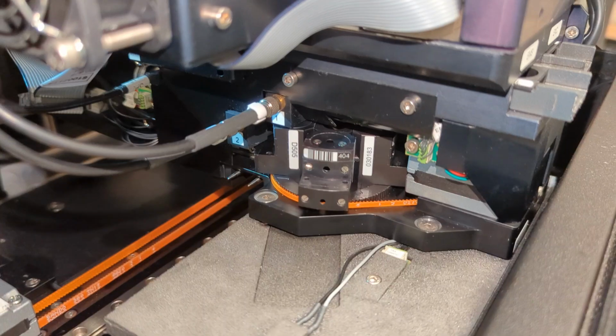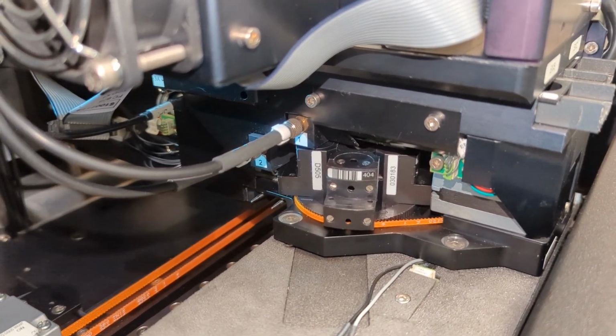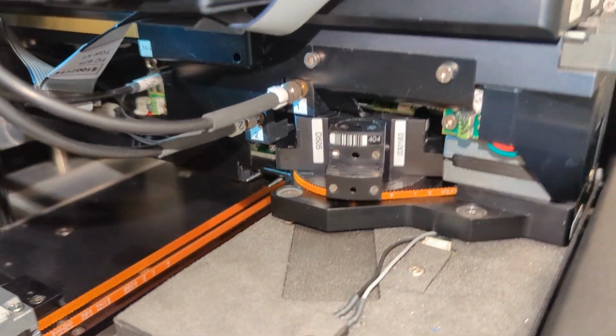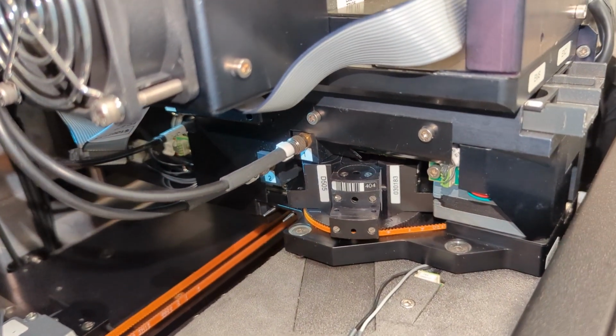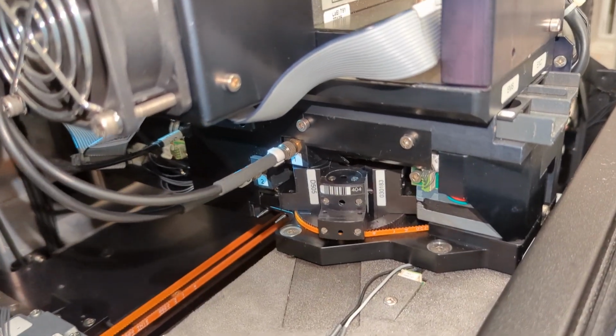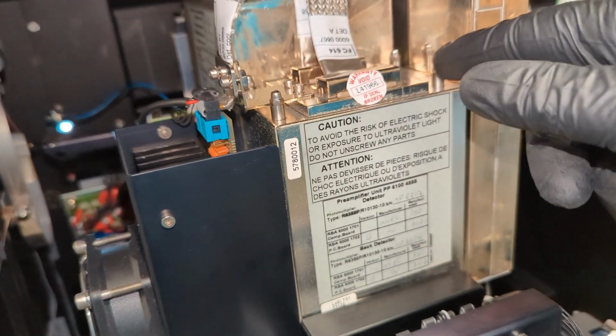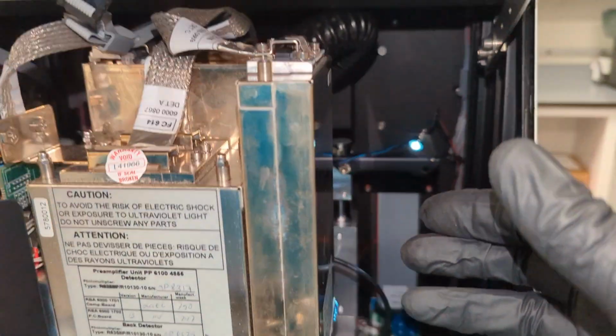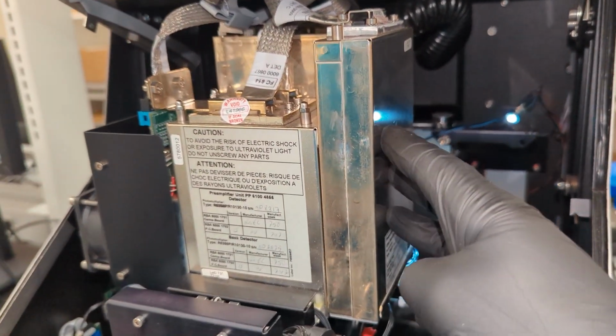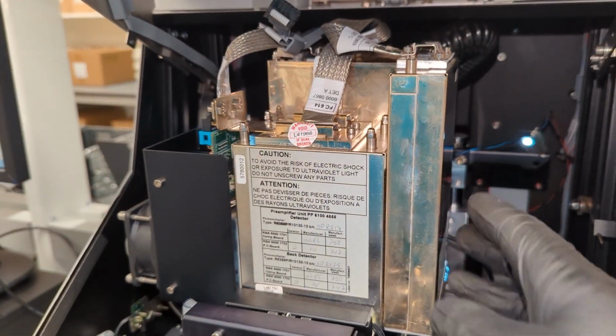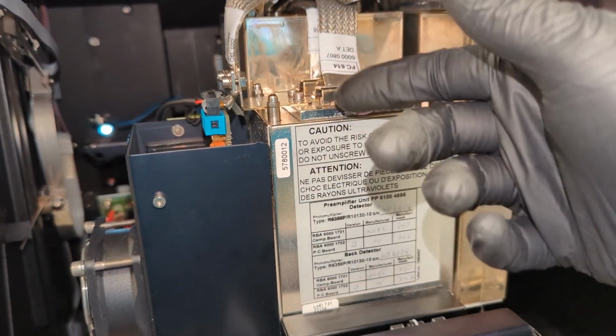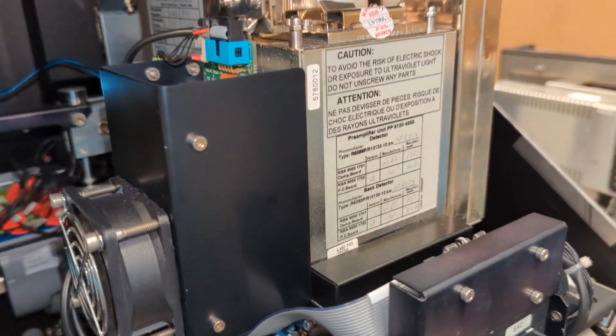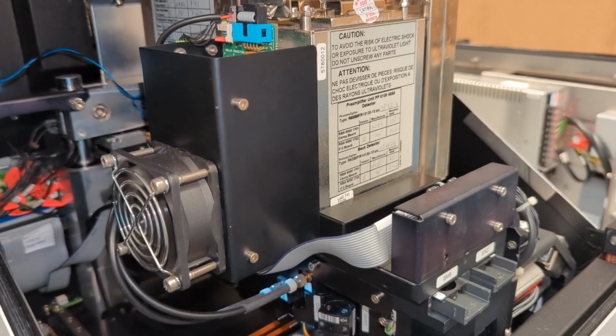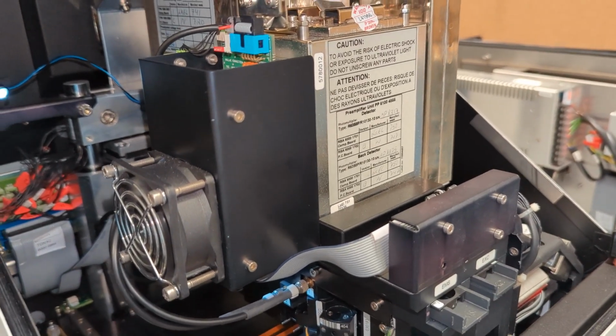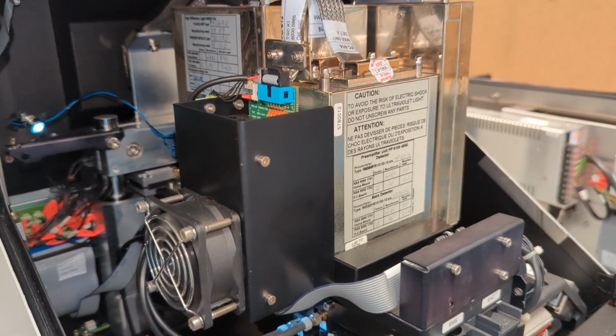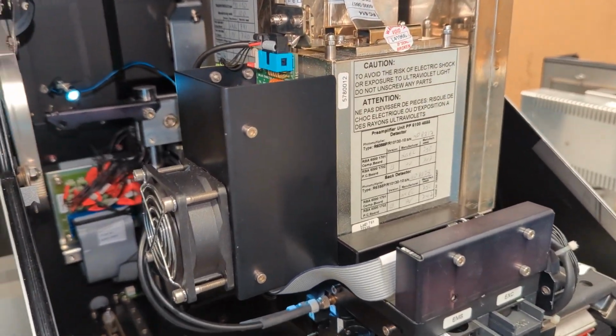All right, so back to the optic path of the light. We're getting pretty close to the detectors, but as I was saying, you can read from the bottom, you can read from the top, and we actually have two detectors right here. We have a detector A and a detector B. We actually have a third detector here, which is our ultra sensitive luminescence detector. This is an add-on option, so generally the instrument will come with both of these, but you've got two detectors for a few different reasons. One, so you can read bottom and top simultaneously, and also you can read two different emission wavelengths at the same time, which can be helpful for certain applications.